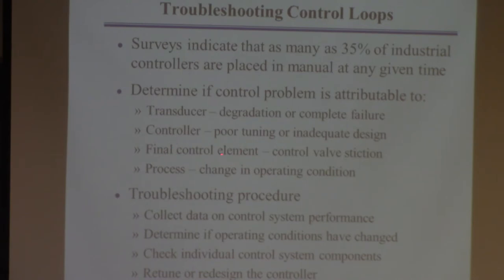You might have a problem with the control valve. This is very common. So the valve isn't working. It's not working properly. It's got hysteresis, so it's sticking. Something like this. And this is a very common problem too - something's changed in the process. When you tune a controller, you're tuning the controller to work for a certain set of process conditions. Like a certain throughput of the plant. If someone changes the process dramatically, like they increase the throughput by 30%, it's very likely your controllers won't be tuned well anymore. And if that's the case, you're going to have to do something.